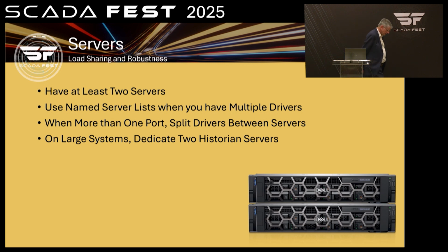When you start to get really big, it's always worthwhile considering putting two historian servers online, taking all the historian work off the main I/O servers. The load in any VT SCADA application goes on the I/O servers, since those are the ones actually communicating with the PLC and taking the most CPU load. If you divide that load, and then offload historians to another machine or two, that will make a notable difference to your performance. This is now getting into big systems, I say big systems, 50,000 tags and more.